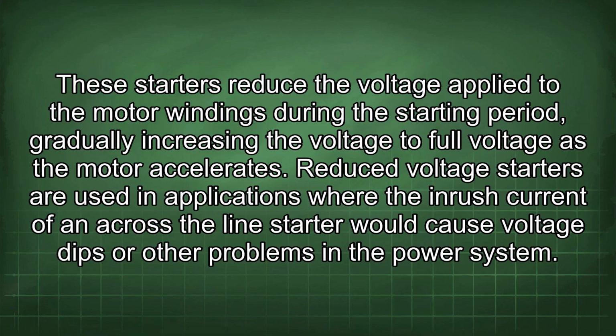These starters reduce the voltage applied to the motor windings during the starting period, gradually increasing the voltage to full voltage as the motor accelerates. Reduced voltage starters are used in applications where the inrush current of an across-the-line starter would cause voltage dips or other problems in a power system.